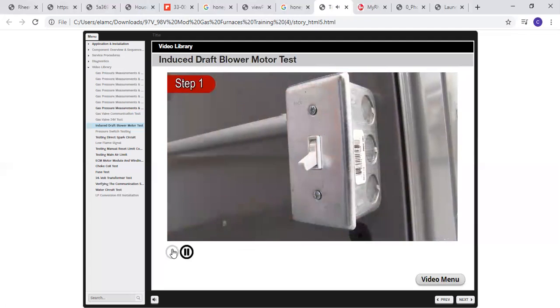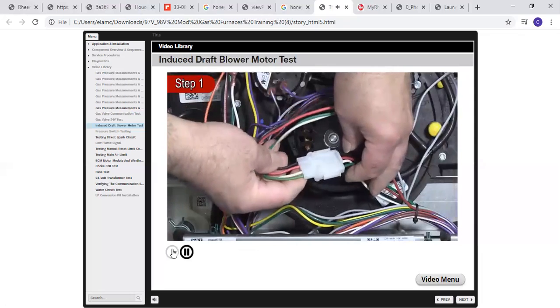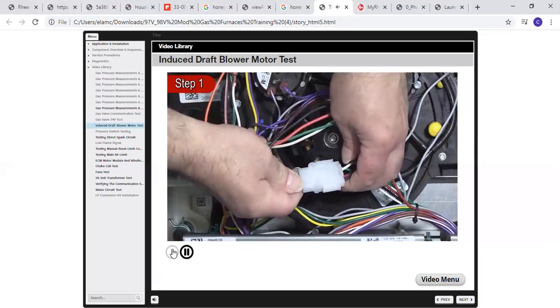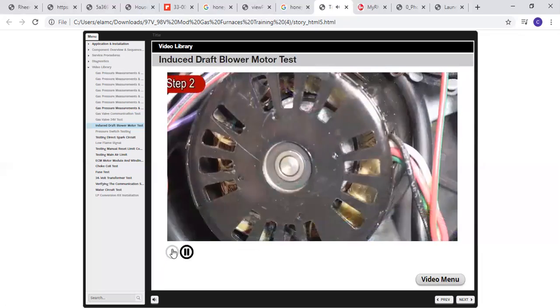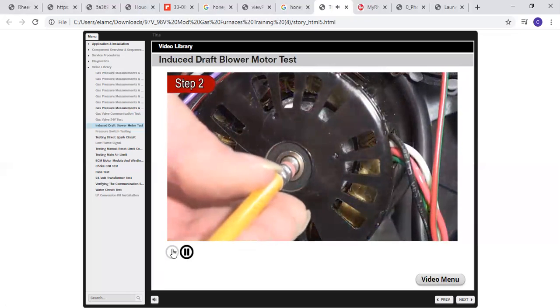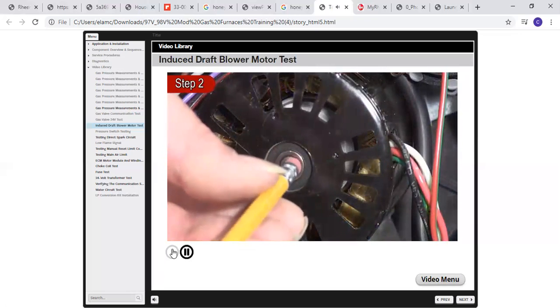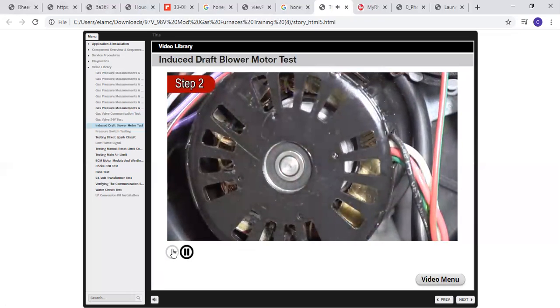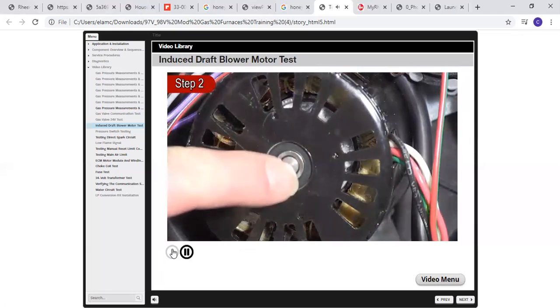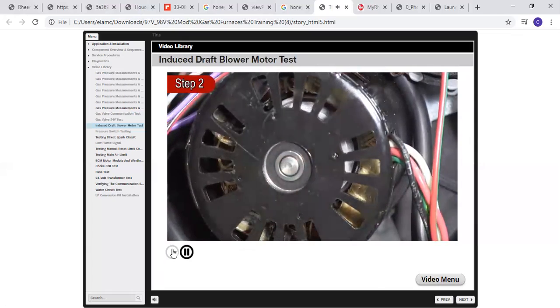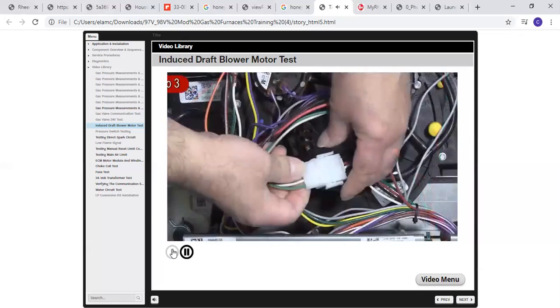Step 1. Shut off power to the furnace and ensure the inducer motor is securely plugged into the wiring harness connector. Step 2. Manually spin the inducer motor shaft and observe if the wheel spins freely. If it does not spin freely, remove the inducer and check for obstructions in the housing. If the wheel spins freely, go to the next step.